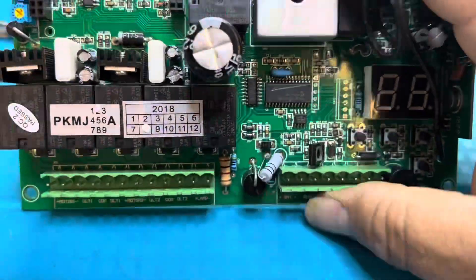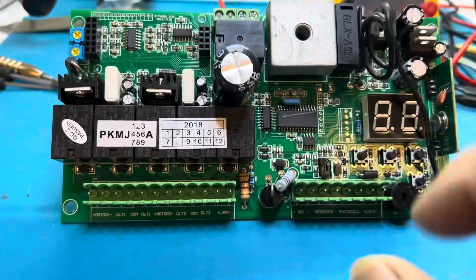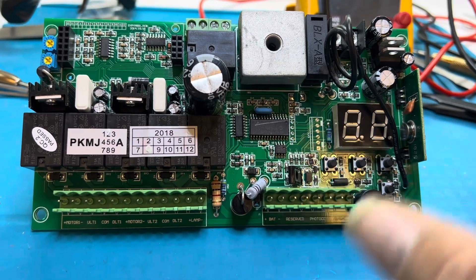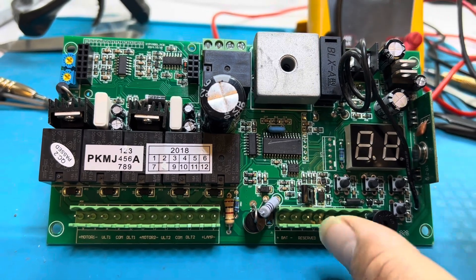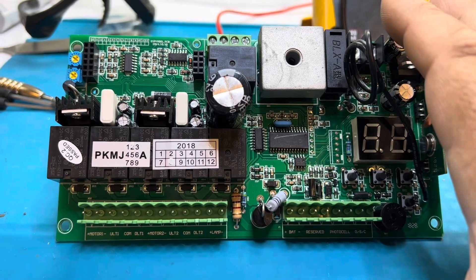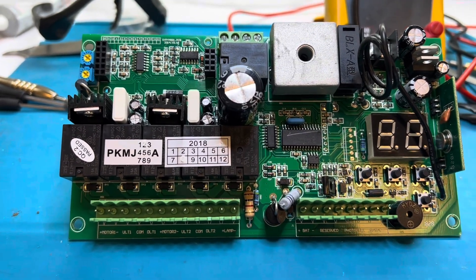I've already repaired this board, but I want to shoot this video because a lot of times a guy will get frustrated with these gate controllers and go buy a whole brand new main board — and that's unnecessary. Unless you've burned up the board, where you smell smoke and open it up to find a whole burned section, at that point you may want to replace it.